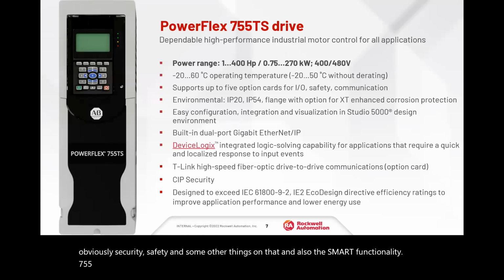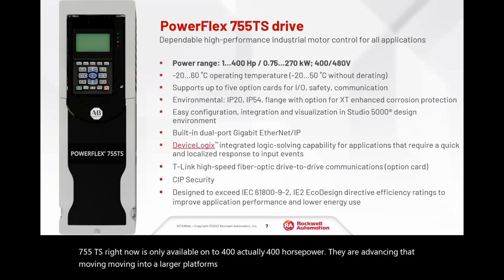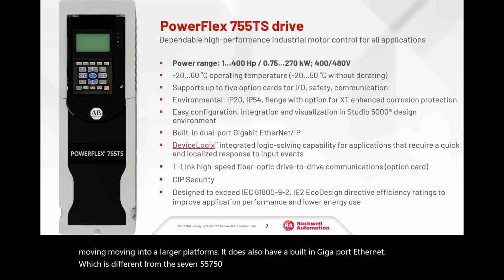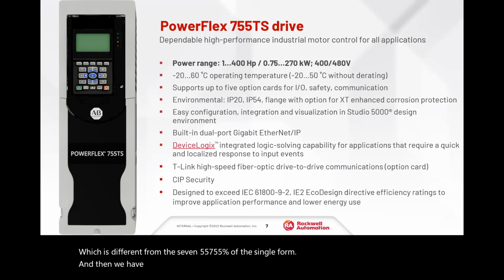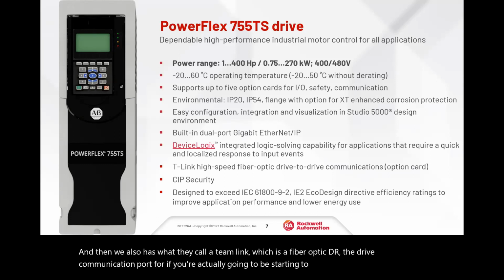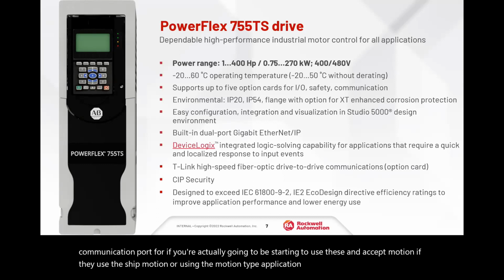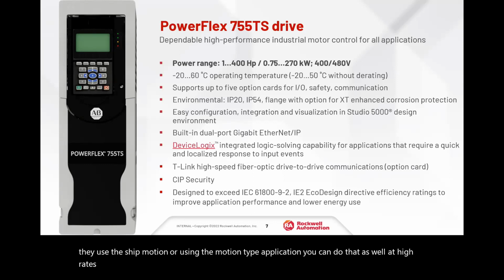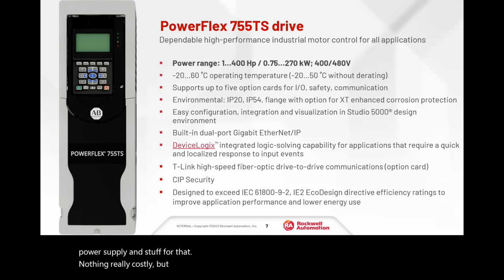755 TS right now is only available up to 400 horsepower. They are advancing that, moving into larger platforms. It does also have a built-in gigaport Ethernet, which is different from the 755. 755 just has a single port. And it also has what they call a T-Link, which is a fiber optic drive-to-drive communication port. If you're going to be using these in CIP Motion or a motion type application, you can do that as well at high rates of speed using that T-Link. That does also involve getting another little power supply for that. Nothing really costly.